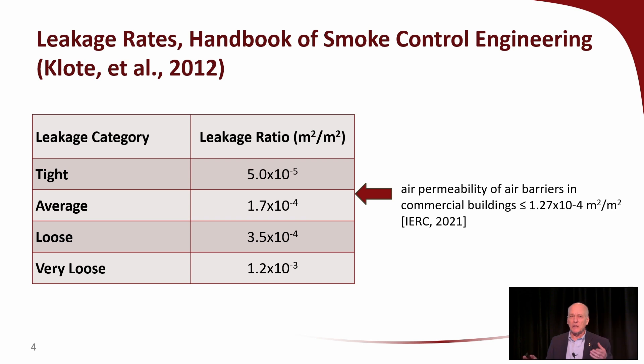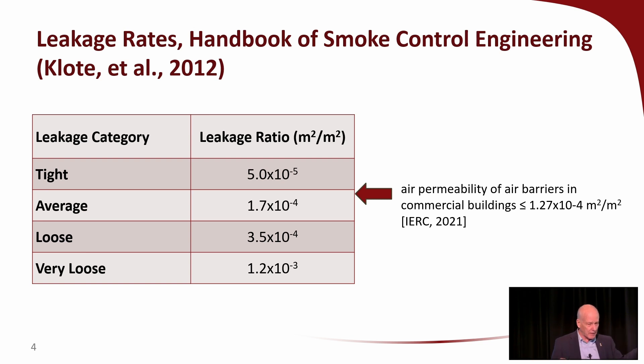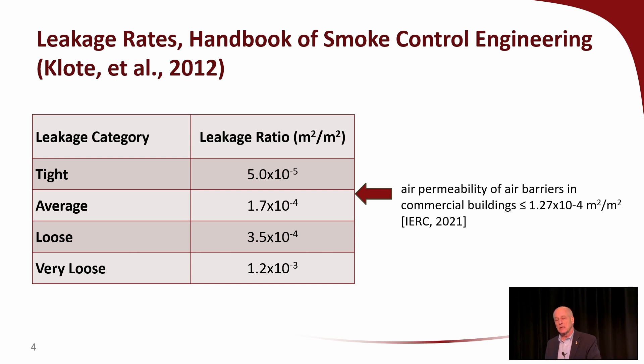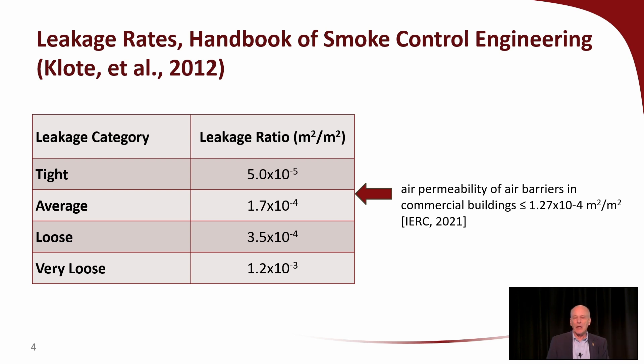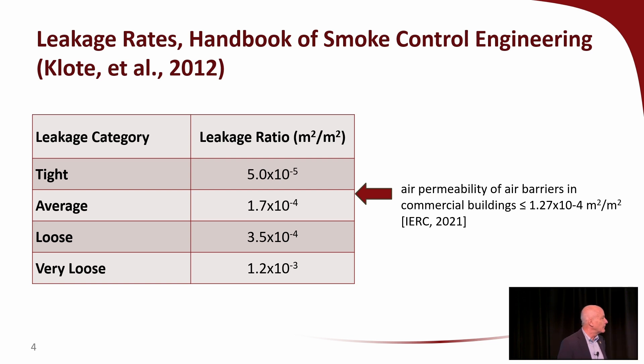Buildings changed in 50 years. Energy conservation wasn't even a phrase we used in the 1970s. So, what's that wall? There's little characterization. As a designer having to use Ventus to do a stairway pressurization system, what do you use? You end up utilizing what we politely call an engineering estimate — that the rest of the world calls a guess, maybe a wild guess. What do you base that engineering estimate on? Sometimes it's trial and error: you run a design with loose or average, that worked, so next project you use loose again.